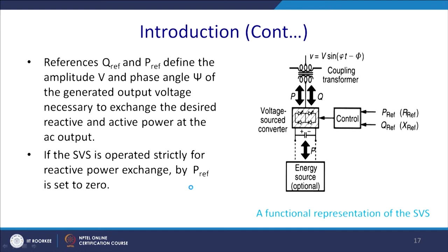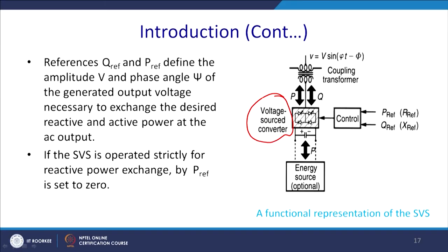This is the configuration. It has a coupling transformer — analogous to the STATCOM solution in the shunt, but connected in series here. The voltage source converter generates reactive power according to the switching, and if connected with just a capacitor to meet the losses and harmonics, it can inject voltage and compensate reactive power. If a storage device is connected, it can also inject real power.